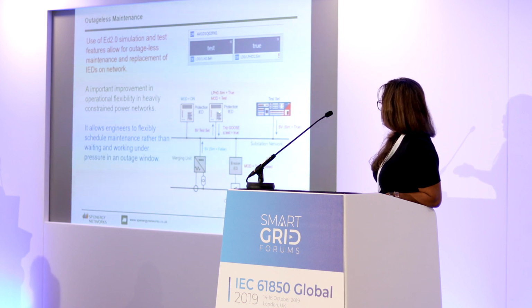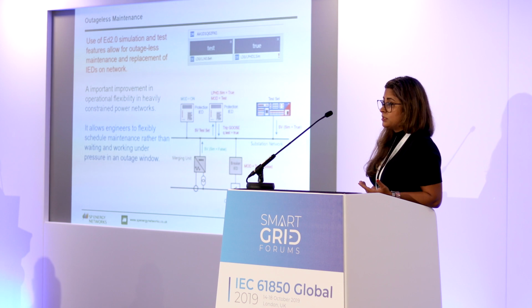You take the IED out of operation, take the signals that go from the IED out to the switchyard, and put them into test block mode as well. So anything the IED does is only being tested with this test set. It's not affecting the real operation of the rest of the system, and your system is still protected because you have a redundant system protecting it.